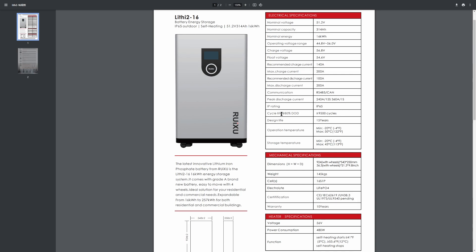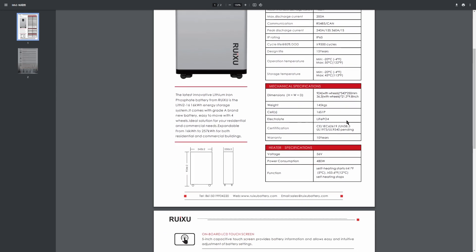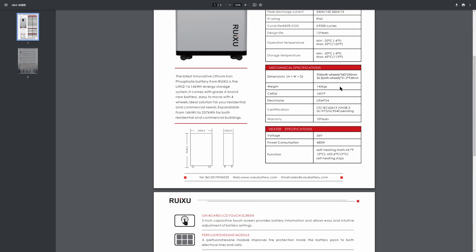Now for the cycle life, if you have an 80% depth of discharge, you're looking at 9,500 cycles and that's about 15 years of daily consistent use. So really long there. Looking at the dimensions of the battery in millimeters and inches. Also the weight is 320 pounds or 145 kilograms. And there are 16 lithium iron phosphate batteries wired together in series on this battery. Now it is pending UL listing, hopefully within a couple of months or even less than that, we should have it UL listed. And it does have a 10 year warranty.